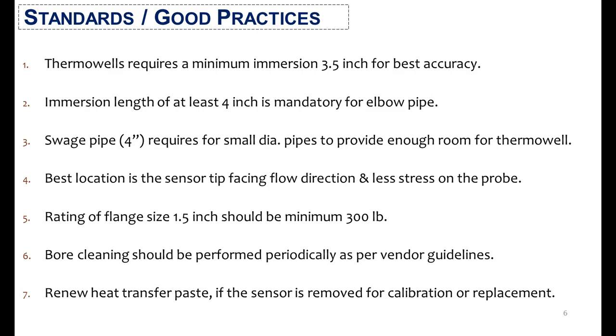The best location of a thermowell is with the sensor tip facing the flow direction, for less stress on the probe. For a flange size of 1.5 inch, the rating of the flange should be a minimum of 300 pound.